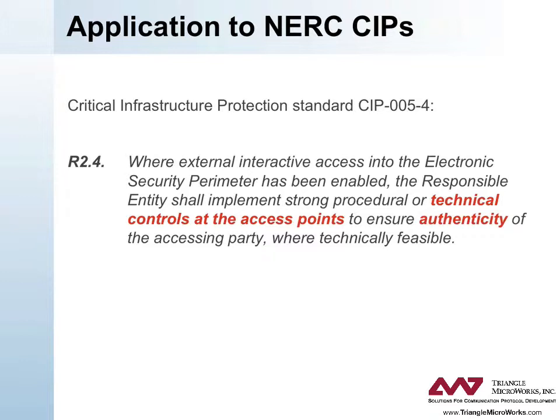Thirdly, some people make the argument that electronic security controls are not required for SCADA or data traffic, only for remote login to a device. Their argument is that the term 'external interactive access' means remote login. It remains to be seen whether this position is defensible. Lastly, the location where DNP3 Secure Authentication may be deployed may vary depending on how your organization chooses to define its critical cyber assets and electronic security perimeter, which in turn may depend on how much power may be switched or shed on a given network. It may be that your organization defines its electronic security perimeter in such a way that some of its access points carry DNP3 traffic. In these cases, DNP3 Secure Authentication is intended to provide a technical control to ensure the authenticity of the accessing party.